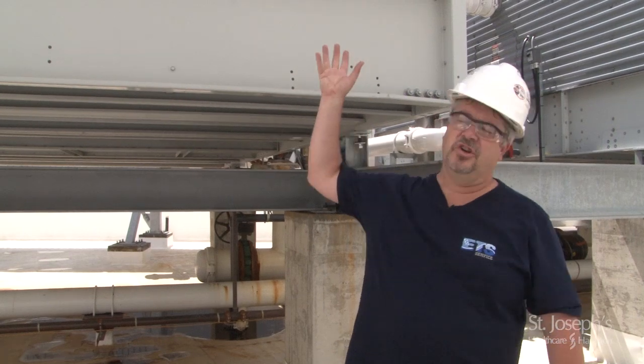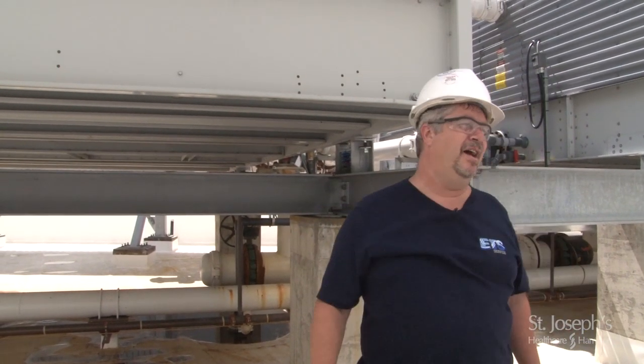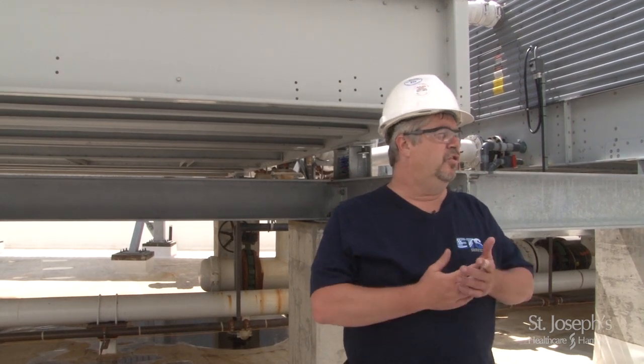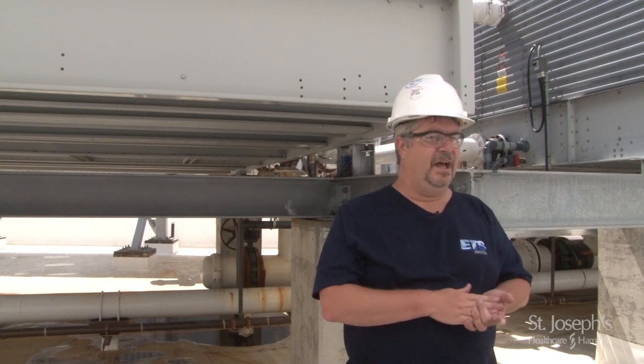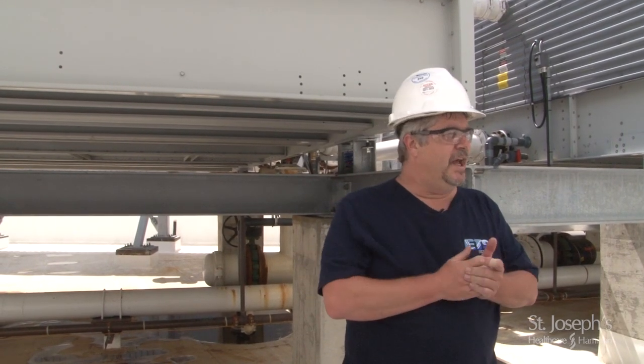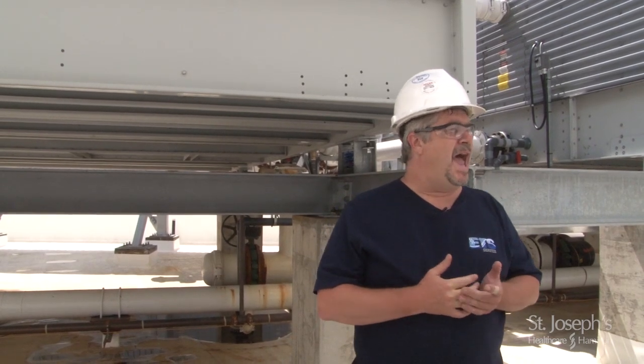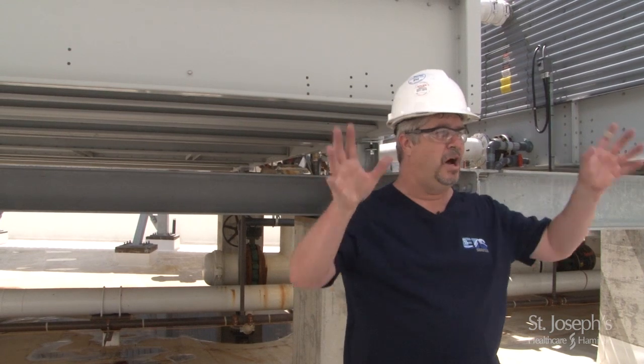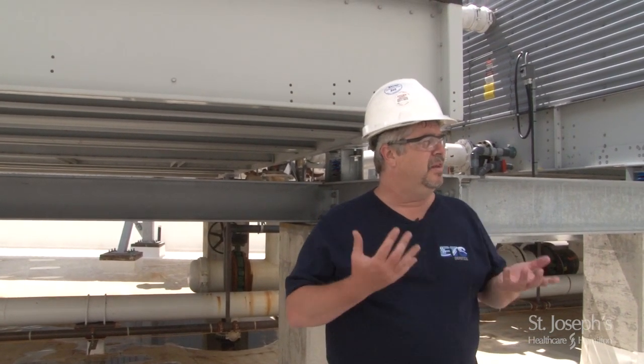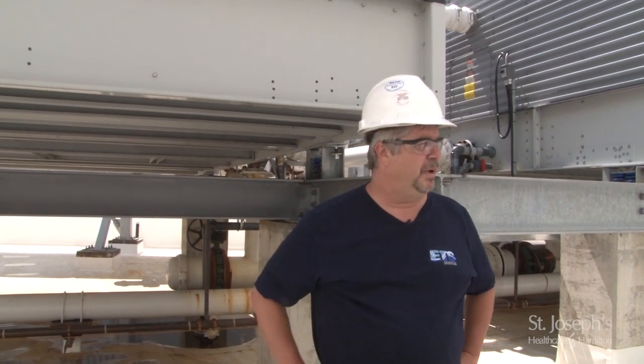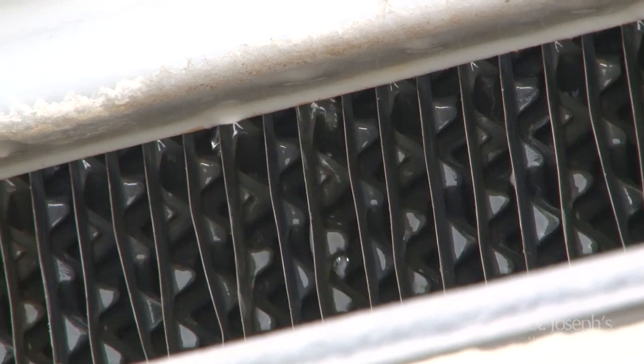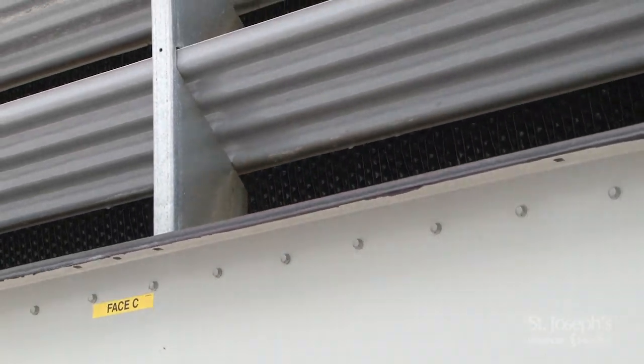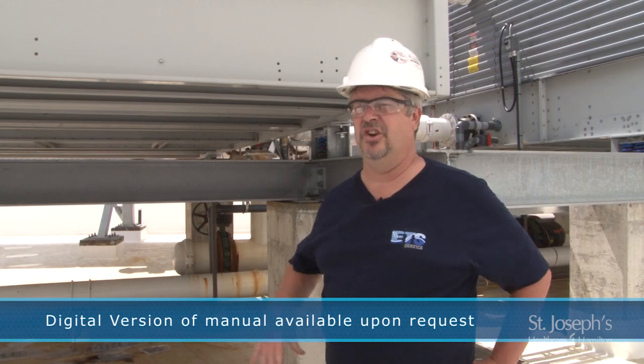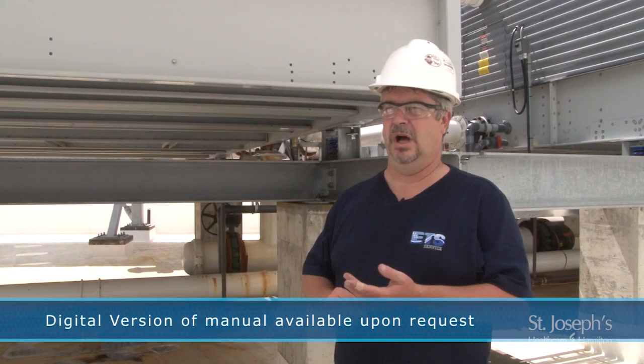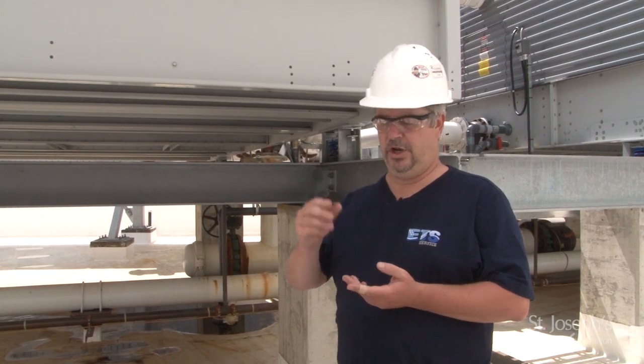If you do see algae or calcium buildup within that fill pack area, what you really need to be doing is talking to your chemical treatment guy. Let him know, I see white calcium or I see a green algae building. He can adjust your chemicals and it will actually clean itself as the tower is running. As the water's running through the tower, the proper chemical treatment will clean those fill packs out all on their own. When you're doing your maintenance, and I will be providing you with the operation and maintenance manual that comes with these towers, it will talk about the intervals of inspection and cleaning. There's a whole chart that tells you what you should be doing monthly, what you should be doing quarterly, and what you should be doing annually.